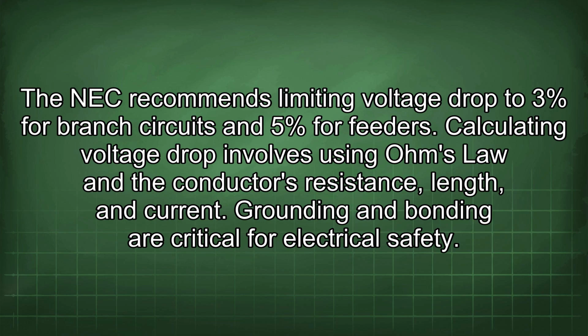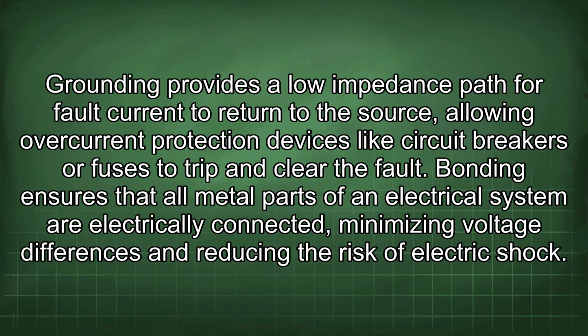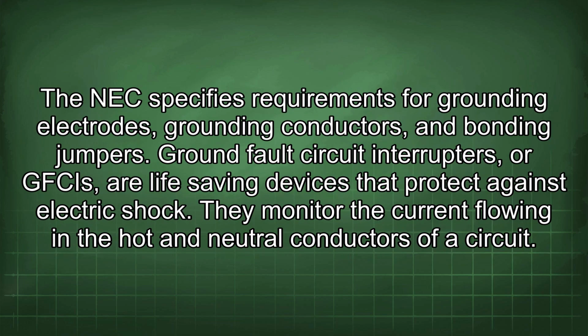Grounding and bonding are critical for electrical safety. Grounding provides a low impedance path for fault current to return to the source, allowing overcurrent protection devices like circuit breakers or fuses to trip and clear the fault. Bonding ensures that all metal parts of an electrical system are electrically connected, minimizing voltage differences and reducing the risk of electric shock. The NEC specifies requirements for grounding electrodes, grounding conductors, and bonding jumpers.